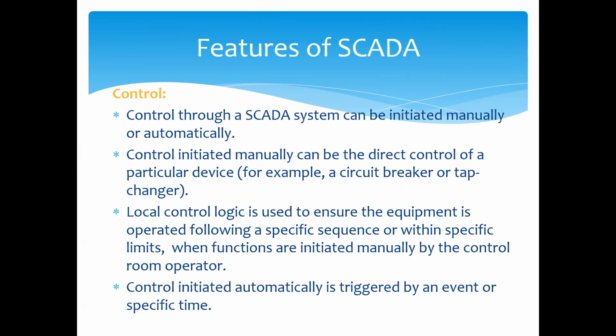Control in SCADA. Control through the SCADA system can be initiated manually or automatically. For example, if we want to switch off a particular device, we can switch it off. But further, for example, if the voltage level goes high due to high solar penetration, we can switch off certain devices by developing an algorithm to cut off those feeders automatically.